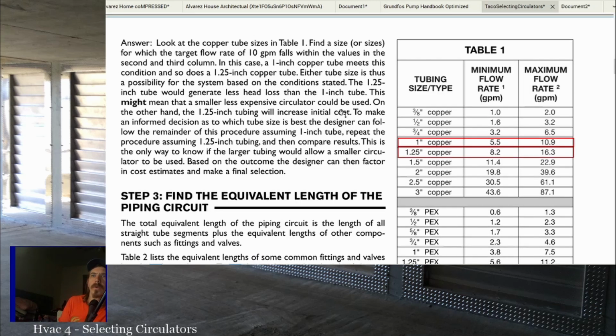So anyway, either one will work, right? The 1.25-inch tube would generate less head loss than the 1-inch tube. As the pipe gets bigger, we're going to have less head pressure loss through the pipe. There's less friction for the volume of water. This might mean a smaller, less expensive circulator. The less the head loss, the less powerful the motor on the circulator has to be, so it's going to be a cheaper circulator.